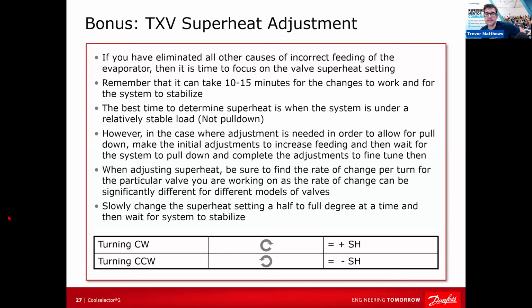Good. Here's the last couple of tips we're going to give you. And I think adjusting superheat is super important, because if you don't adjust it at the right time after certain conditions and you leave, you could run into a massive issue. Because I've done this before. I've set superheat, the guilt's setting in, and I'm gone. And then I come back and I'm like, oh my God, why is it so white?